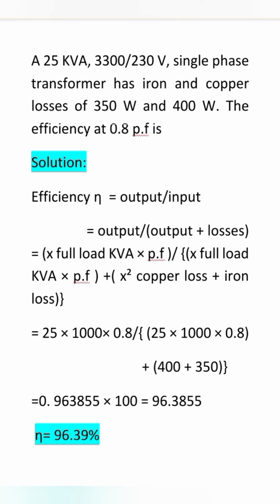Substitute x is equal to 1, full load kVA is 25,000, and power factor is 0.8. Copper loss is 400 and iron loss is 350. We get efficiency is equal to 96.39 percent.